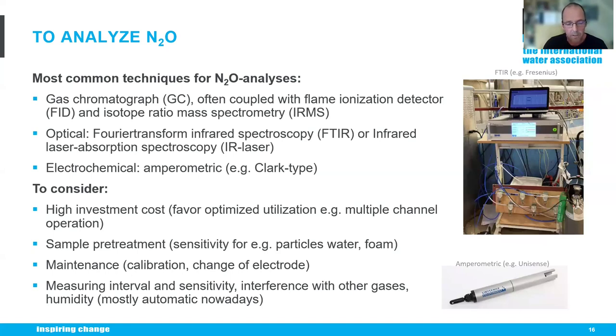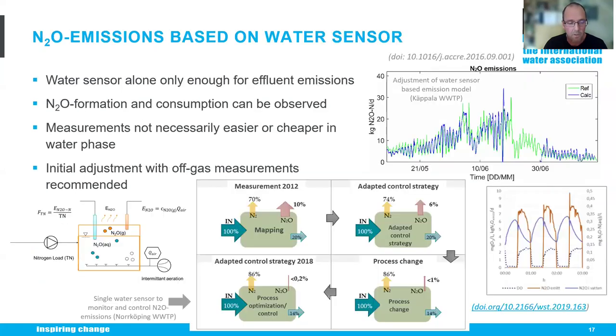Regarding water phase measurements, the water sensor is sufficient if you measure in the effluent of a wastewater treatment plant — you have the water flow and N2O concentration so you can quantify emission to the receiving water. Otherwise, water sensors are good to measure the formation and consumption of N2O in different processes, and by that you can ultimately control the process. Unfortunately, water phase measurements are not necessarily easier or cheaper — they require high investment and a lot of maintenance.